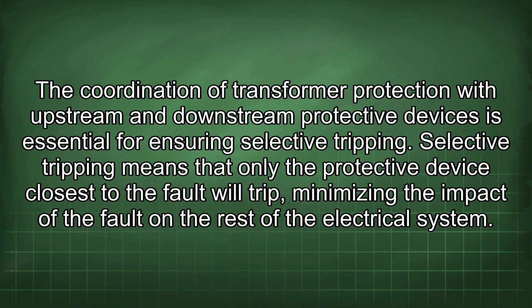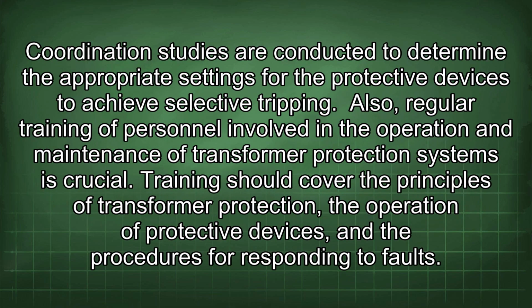The coordination of transformer protection with upstream and downstream protective devices is essential for ensuring selective tripping. Selective tripping means that only the protective device closest to the fault will trip, minimizing the impact of the fault on the rest of the electrical system. Coordination studies are conducted to determine the appropriate settings for the protective devices to achieve selective tripping.